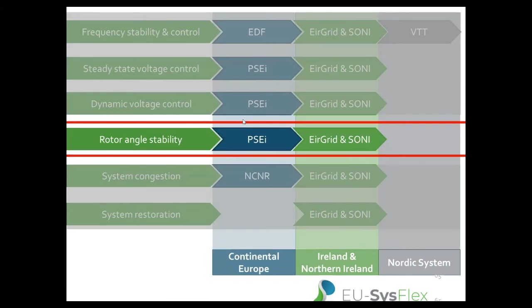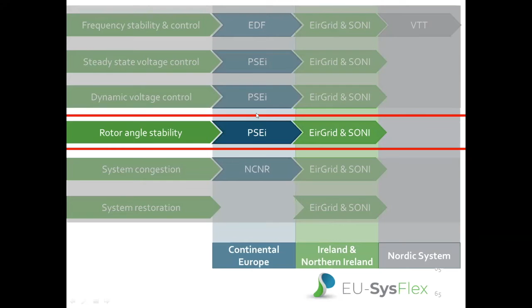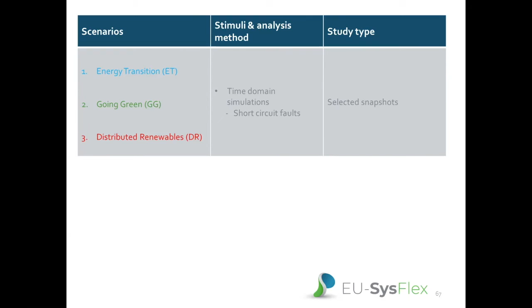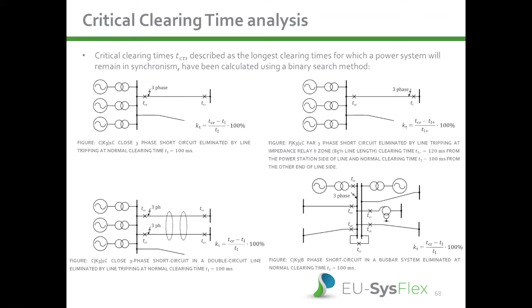Thank you. So for the purposes of rotor angle stability studies for the Continental European power system model, we have applied the same three capacity scenarios as for the steady state and dynamic voltage control. We have also performed dynamic time domain simulations representing electromechanical phenomena in the system. The analysis has also been carried out for selected snapshots. Critical clearing times, which have been calculated, are described as the longest clearing times for which the power system will remain in synchronism. They have been calculated for a presented set of assumed network fault events. Presented disturbances at normal clearing fault time have been investigated.